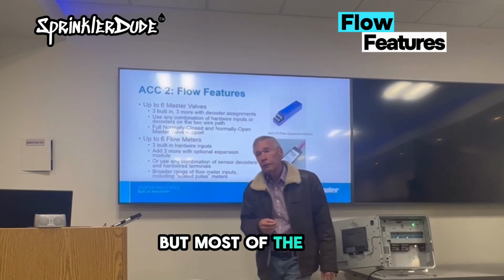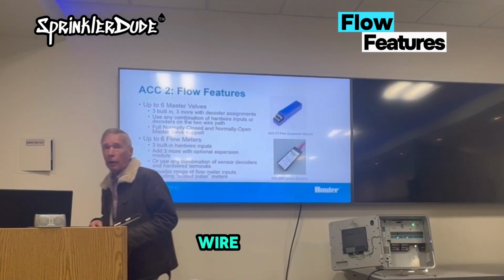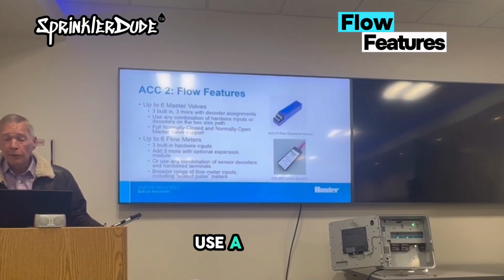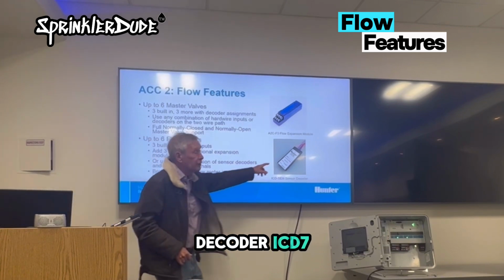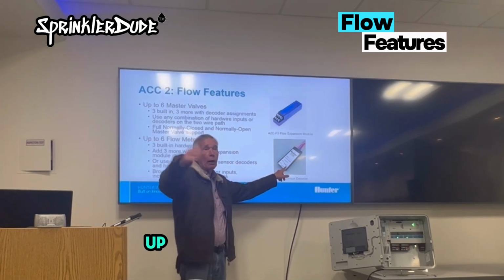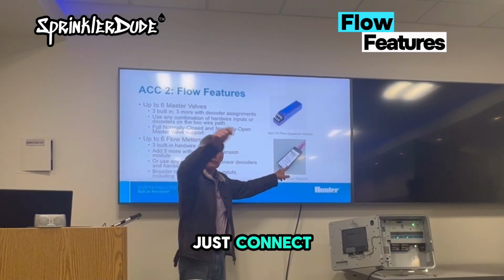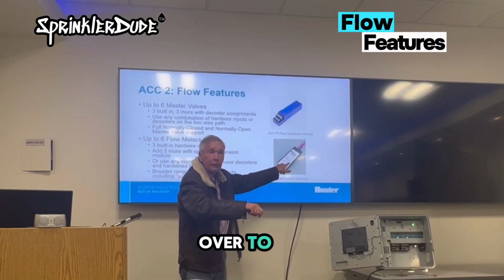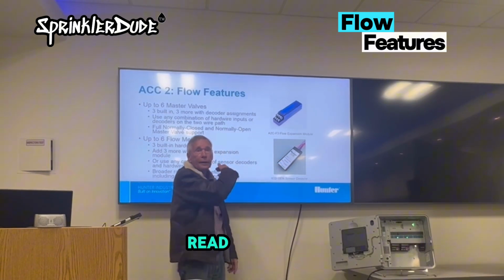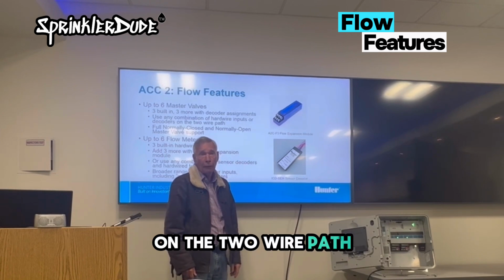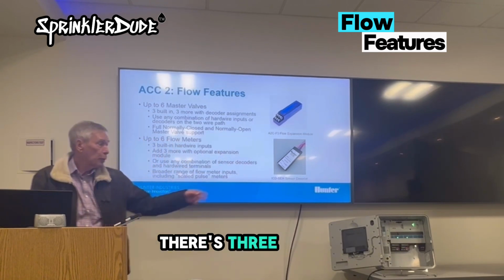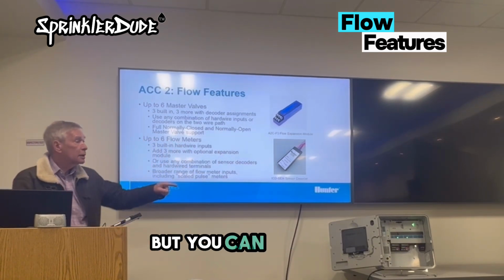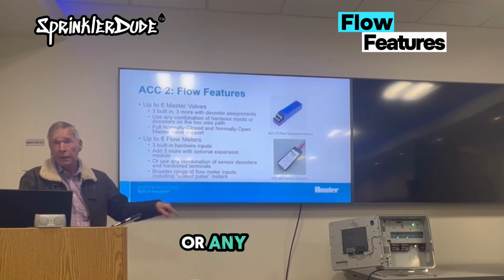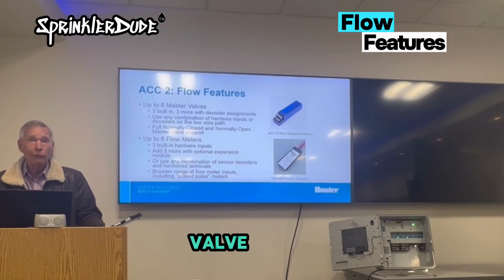But most of the time when that comes up, it's in a 2-wire system. For that, we use a sensor decoder, ICD Sen, and that can be anywhere out in the 2-wire path. Just connect your flow meter over to the sensor decoder, and it will read upstream on the 2-wire path. Same with your master valves. There's 3 master valve outputs, but you can designate any station or any decoder as a master valve output.